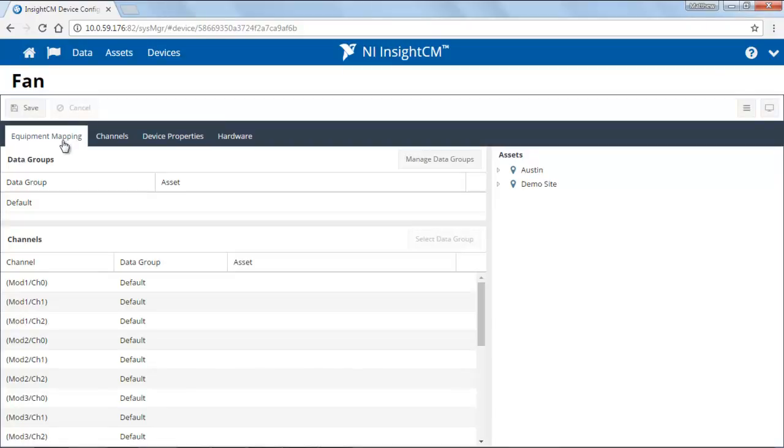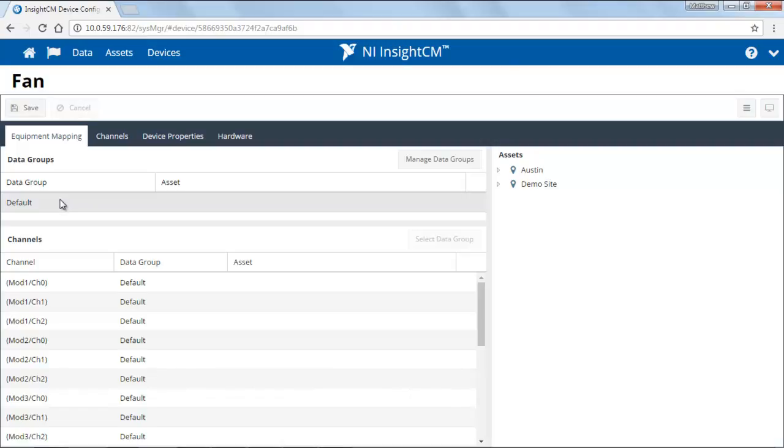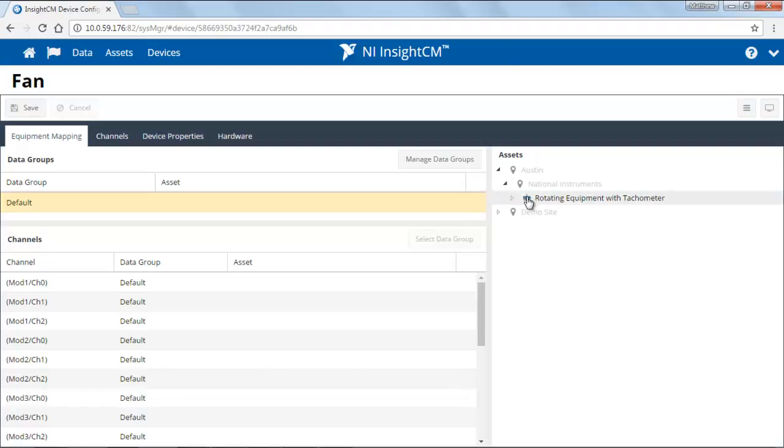The first tab, the Equipment Mapping tab, allows us to do this mapping. Data Group is a collection of channels on the device which are typically linked to a specific asset. To map the Data Group to an asset, click on it and then find the asset of interest. In this case, this device is associated with the rotating equipment with tachometer that I've created earlier.